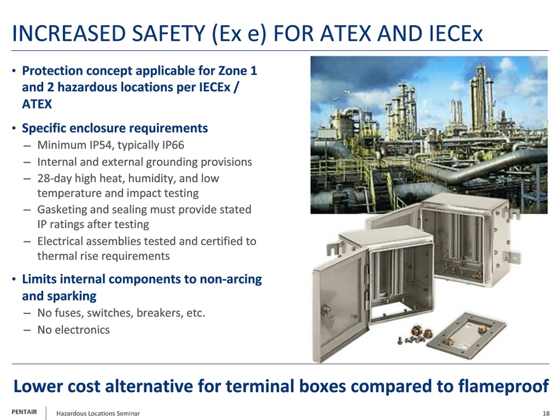They've been tested for high heat, humidity, low temperature, and then there's a lot of impact resistance testing that has to occur. And then you go through that testing, and the IP ratings have to be maintained after it goes through that pretty rigorous testing profile. Another thing that happens is that the entire electrical assembly is tested and certified for thermal rise. So the key here is you're using non-arcing, non-sparking equipment like terminal blocks or operators like a pilot light or a switch that's certified for a Zone 1 or Zone 2 area.